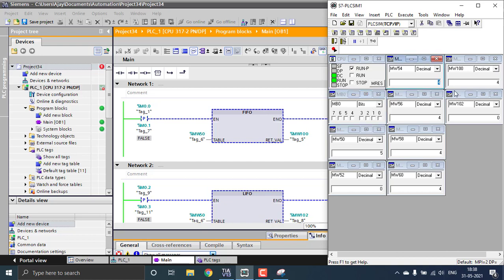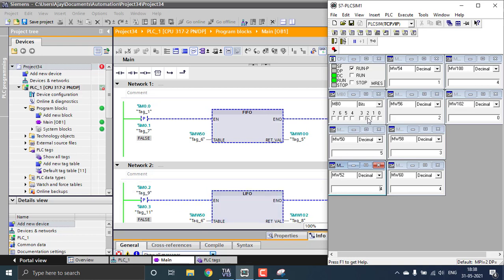Now let's watch the LIFO. Entering values again: one, two, three, and four. The current number of values is four. By triggering M0.2 for the LIFO, the return value goes to MW102. The first value popped up is four, then triggering again gives three — Last In First Out. The last fitted value gets output first. That is the difference between FIFO and LIFO inside the TIA Portal.